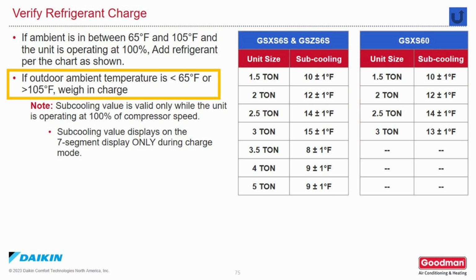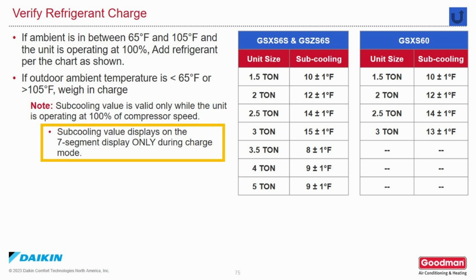If the outdoor ambient temperature is less than 65 or more than 105 degrees Fahrenheit, weigh the charge in. The subcooling value is only valid while the unit is operating at 100% compressor speed. Subcooling values are shown on the display board of the outdoor unit only during charge mode.